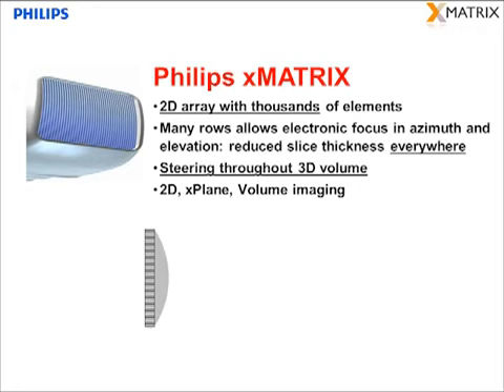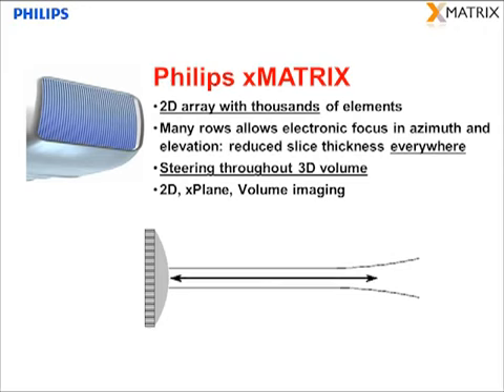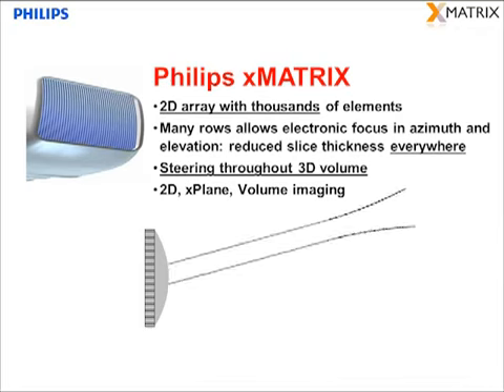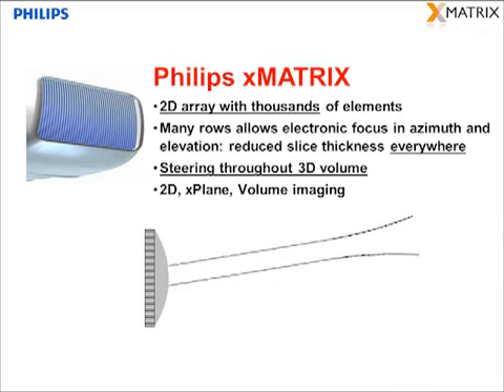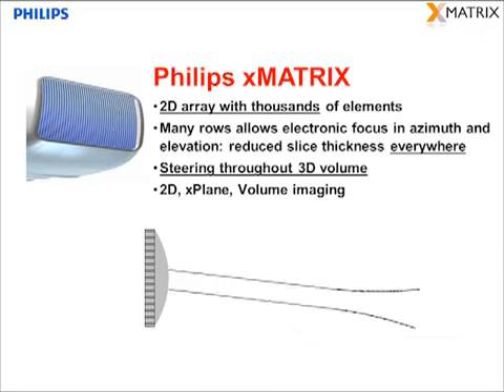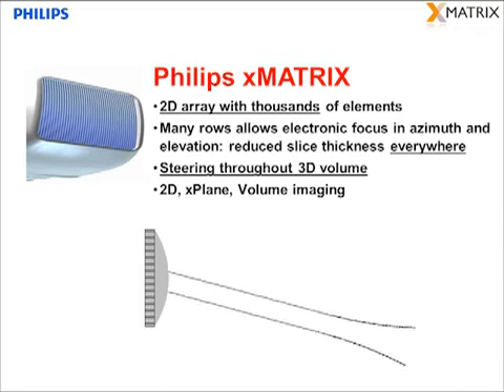In an xMATRIX array, the elevation dimension is separated into elements in the same way that it is in azimuth, with many rows. Having many rows with independent delay control provides the same degree of electronic control of the acoustic beam in elevation as there is in azimuth. We can focus the beam over a much larger focal length, resulting in good slice thickness everywhere. We can also use this electronic control of elevation to steer the acoustic beam throughout the entire three-dimensional field of view. This provides novel modes such as X-plane with two planes displayed simultaneously in real time, as well as 3D.